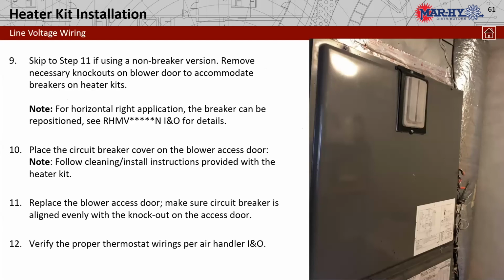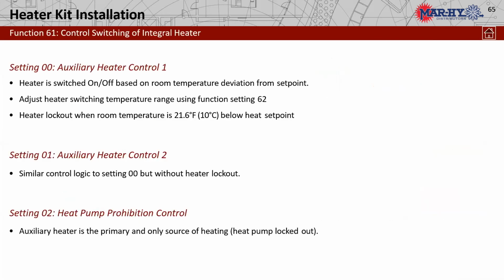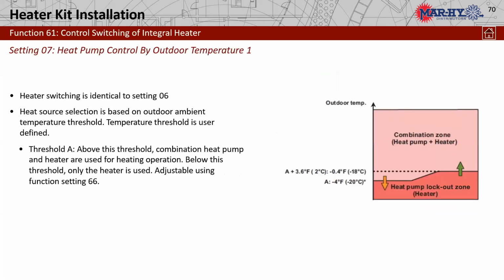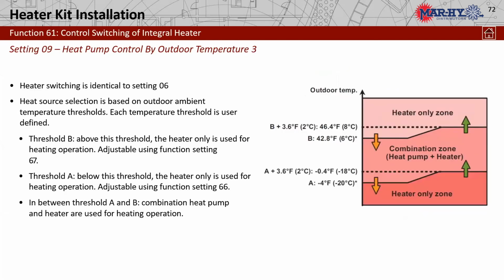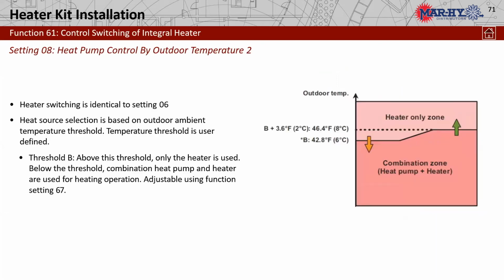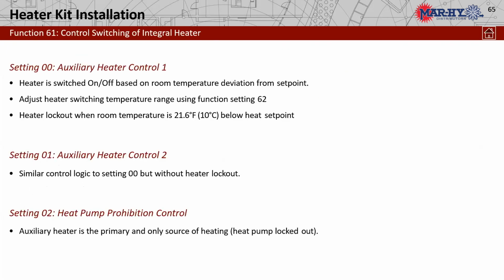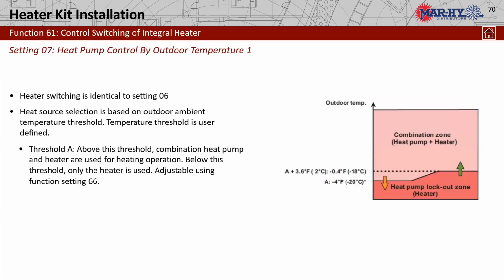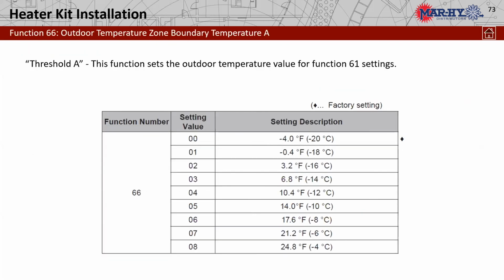There again, our knockouts for our blower covers are exactly what we would do with our conventional air handlers. So this here, the outdoor integral heater control, setting number 9, it shows how they've actually got the strip heaters to be locked out via outdoor, indoor, with the strip heats, and then a lockout of the heat pump below -4 degrees. This is a combination. As you can see, there are several different combinations. And I have chosen combination number 3.